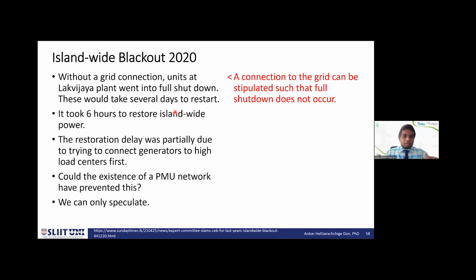Now, for example, this station needs a power connection. Although it is disconnected, it still needs power to not go into a full shutdown. So this can also be stipulated in the PMU algorithms, where it will still be provided a small amount of power so that it doesn't go into full shutdown mode. That takes many days to restart.